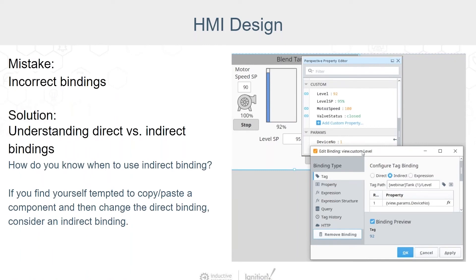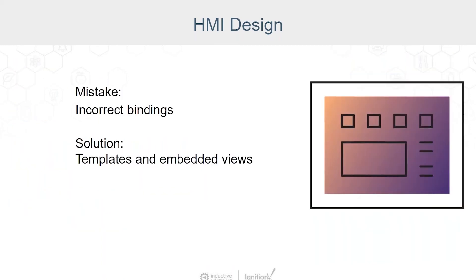For our last HMI design mistake, we're going to take a look at incorrect bindings. This ties back in with the previous topic of data collection and tag allocation. Recognizing when to use direct versus indirect bindings improves data collection efficiency and helps to create a more dynamic system. Whenever you find yourself tempted to copy-paste a component and then change your direct bindings, that's the time to consider an indirect binding. Back to the theme of reusability, understand when to use templates and embedded views — you've already put in the work of designing views and components, so why build them again?